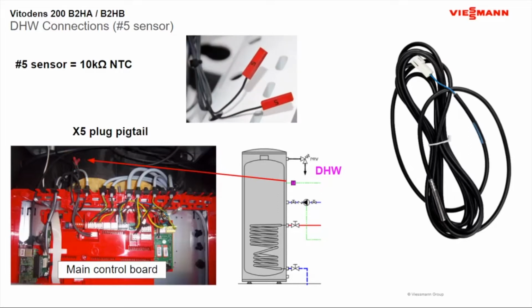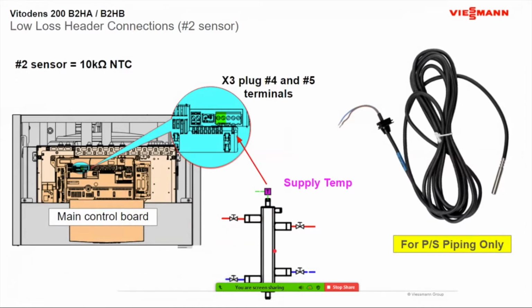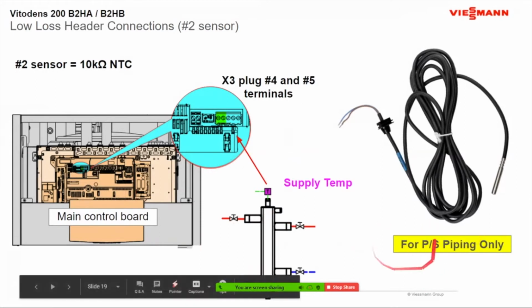The only thing I always like to say about that is just be aware of, let me go back here a couple. If you're doing a low loss header, or no low loss, and your domestic is on this side, your primary side, your boiler side of it, it's set up that way in programming. If you find that your domestic's on the other side of your low loss header, on your system side, if you have a header or something that is coming off of it, you have to go into programming. I believe it's 5B in domestic, and you now have to tell it it's on the other side of the low loss header. Because remember, we have a pump underneath that boiler.